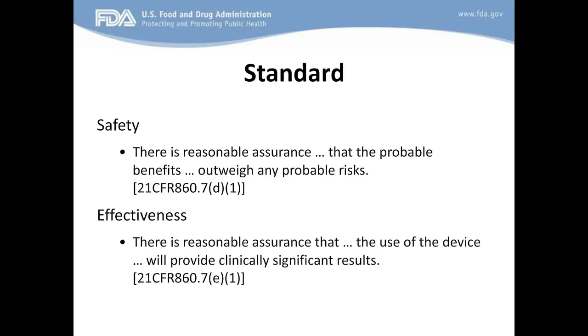The program under which we regulate is, again, risk-based. It defines three different classes of risk, that is, risk to the patient. Class 1 is low-risk devices, Class 2 is more complex or higher-risk devices, and Class 3 is the highest-risk devices. The paradigm defined that for all devices, there were some general controls that all manufacturers had to have, and we'll go through what those general controls are in the next slide. For the lowest-class devices, the general controls were the only things they had to have. They did not have to come to the agency for review before they went to market.